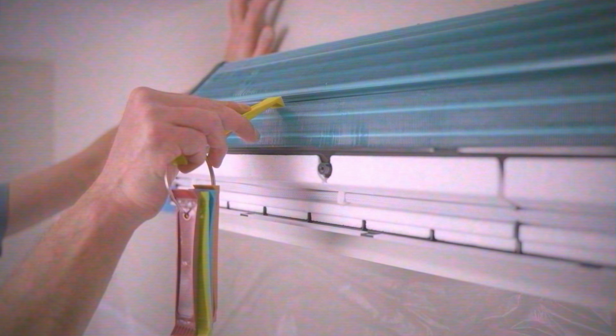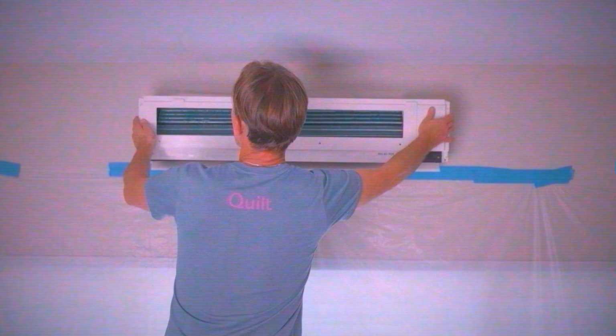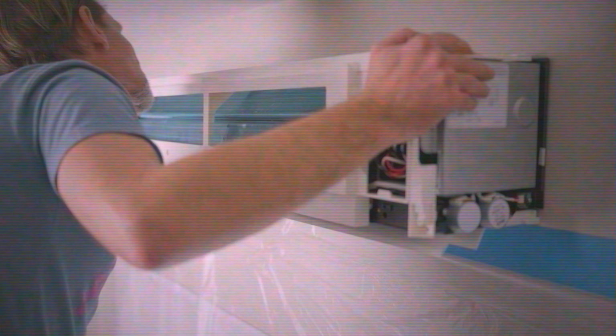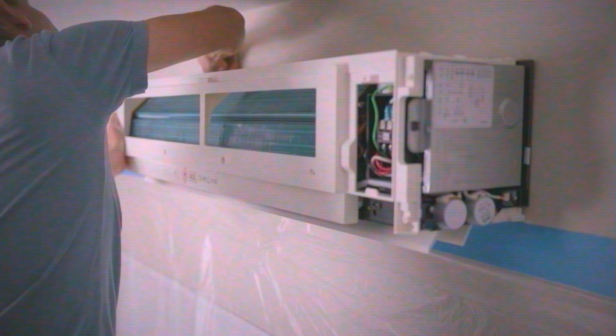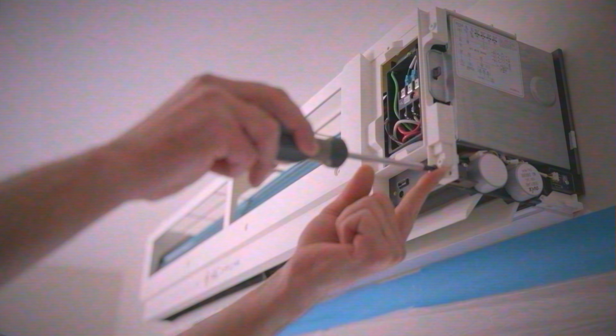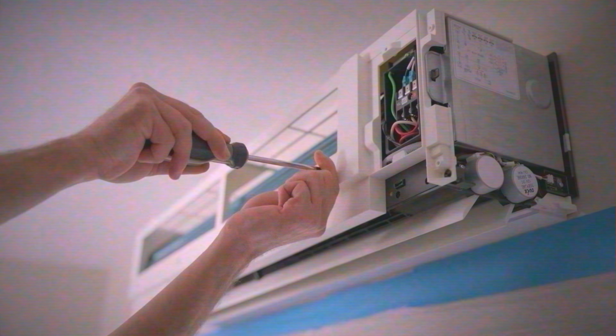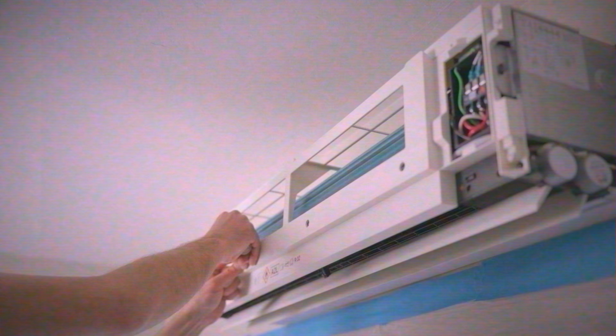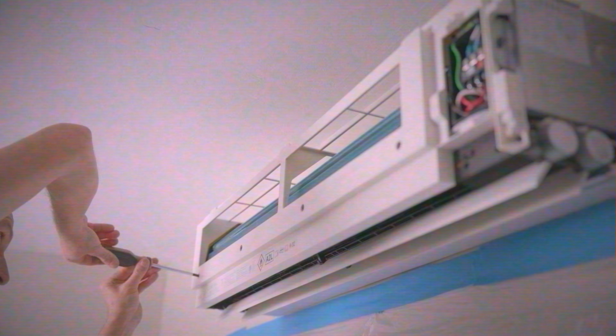Hand tighten the 2 securing screws on each side of the heat exchanger. If you notice any bent fins, use a fin comb to straighten them. Next, reattach the central housing. Align the black tabs at the top, then press down until the tabs click into place. Use a screwdriver to install the 6 screws, making sure not to over-tighten. Then double check that the tabs in the back are still secure.